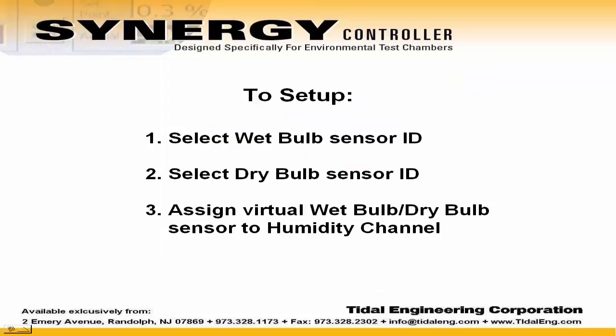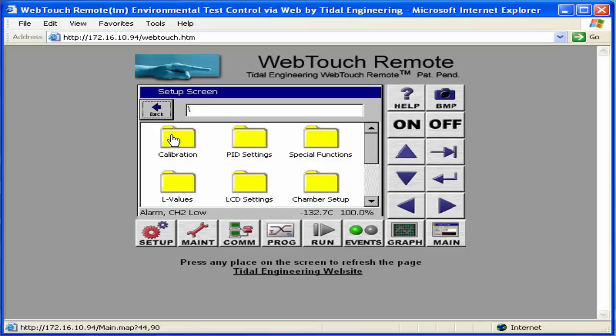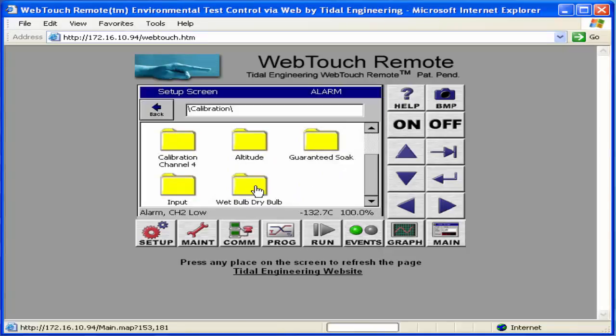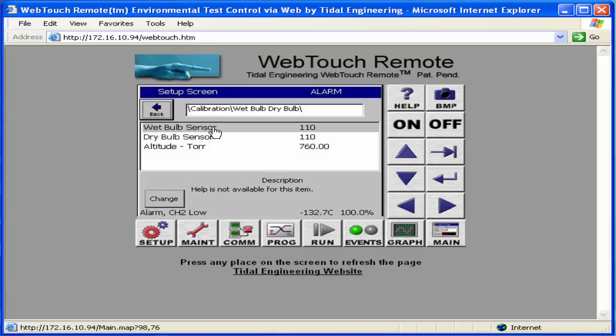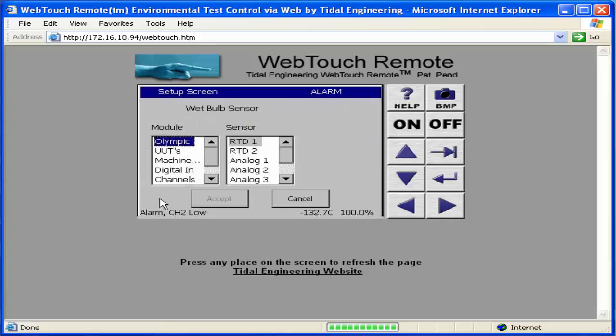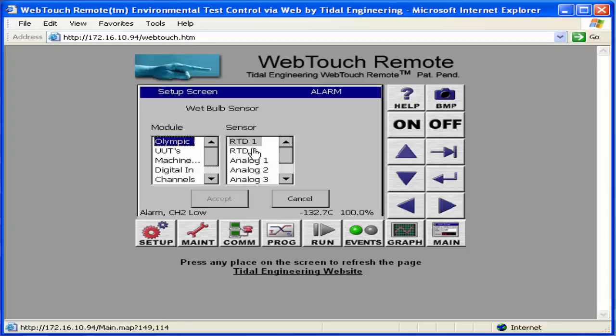Setup includes 3 simple steps. Select the wet bulb sensor ID, select the dry bulb sensor ID, and assign the virtual wet bulb dry bulb sensor to the humidity channel. First, I click on the calibration folder in the setup screen. I then scroll down to the wet bulb dry bulb folder to select the wet bulb sensor ID. Click the Change button, select the RTD2 sensor in the sensor list, and press Accept.